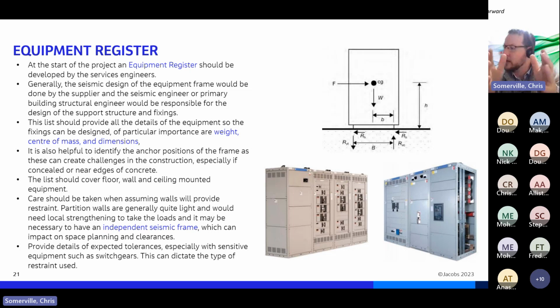And it needs to be factored in. It's quite hard, especially with a stud wall, to coordinate and make sure they're putting in back-to-back studs or closed studs at locations where you've got wall-mounted equipment. Sometimes you may need to create a seismic frame independent of the wall to support the equipment, which has space implications and can impede some clearances. So that needs to be worked through early in the design.